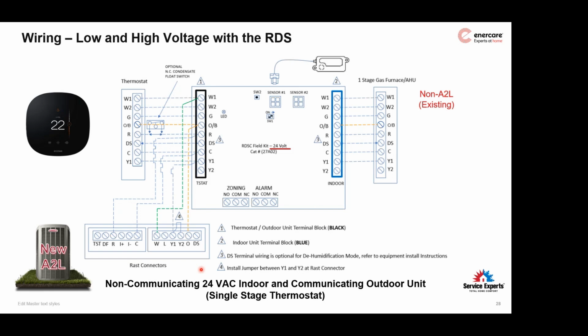The one trick is, of course, when we're putting together fossil fuel heat systems and heat pumps, they are not really designed to run simultaneously. So the thermostats are set up to prevent that. But during defrost is kind of the exception.